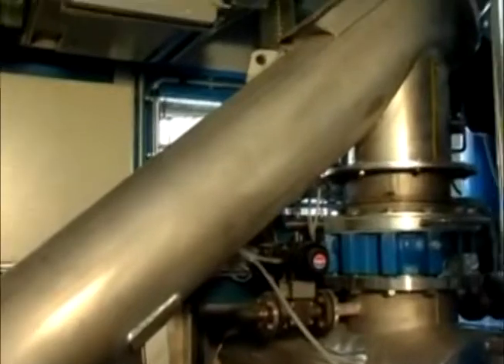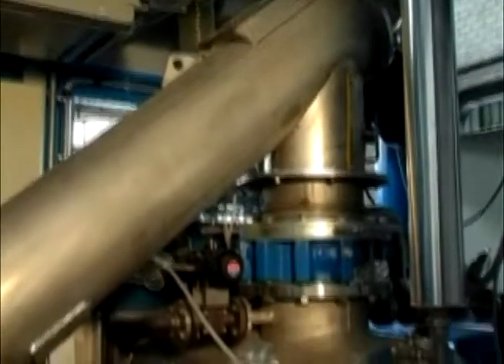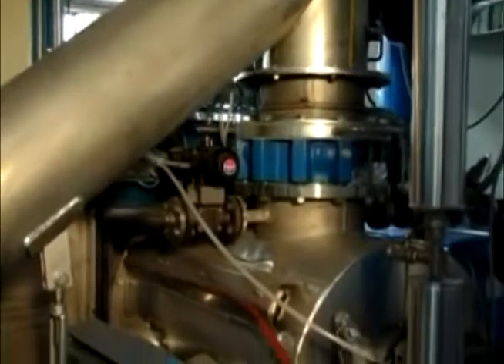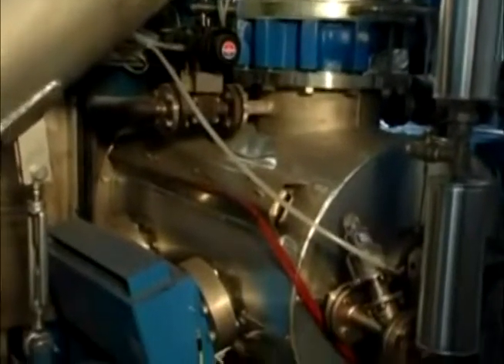The waste, reduced to small pieces, is ready to be transferred to the sterilization chamber through an inclined cochlea. The material arrives at the mouth of the sterilization chamber, where the entrance is controlled by a guillotine valve, which interrupts the loading when the set loading time is finished. This way it is possible to keep the waste of the sterilization phase separate from the waste of the loading phase.